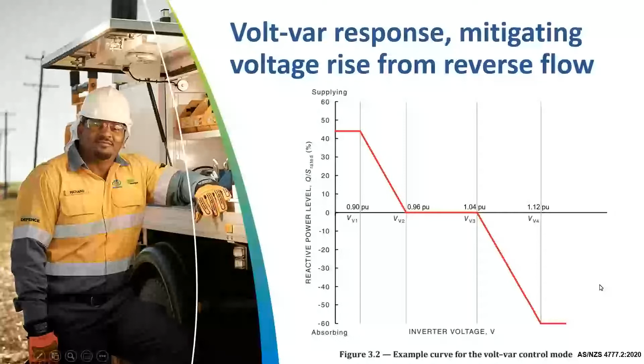Another key factor that Jenny briefly touched on is smart inverters and the requirements in 4777 Part 2. Specifically, I wanted to refer to the voltage response modes: volt-var, which requires inverters to absorb reactive power when the voltage is above 240 volts and also support voltage levels when voltages go very low; and volt-watt, which requires a limit on the maximum active power output when voltages exceed 253 volts.